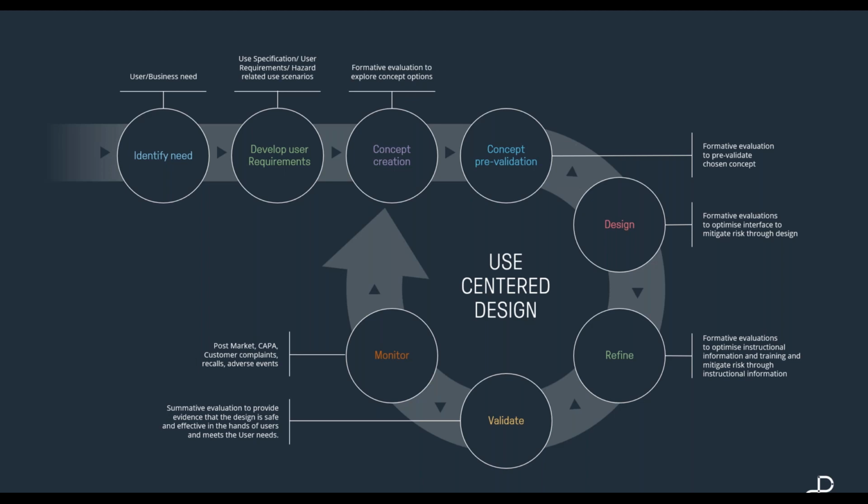So usability engineering does have a role to play before there's even a user interface in play, by really understanding the workflows and the people and the environments involved that are central to the design of a medical device. Once a concept exists and has been created, this is when formative evaluations can begin, whether desk-based or within simulated use, in order to explore different options for an interface.